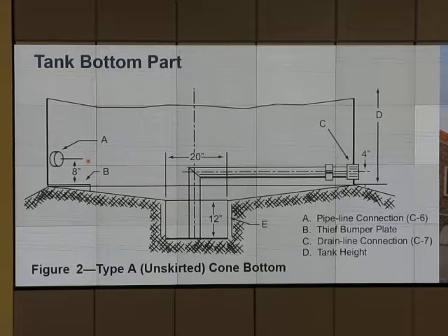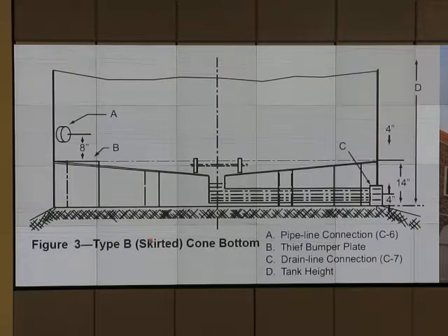Okay, tank. Some tanks have a bottom part for the drain, to collect the solid part. We can pump out anything from the bottom. So if you accumulate any sand, any BS&W over there, then we can pump it out. With those tanks, you will see that from time to time you may have to pump and circulate it to get a representative sample if you want a sample.